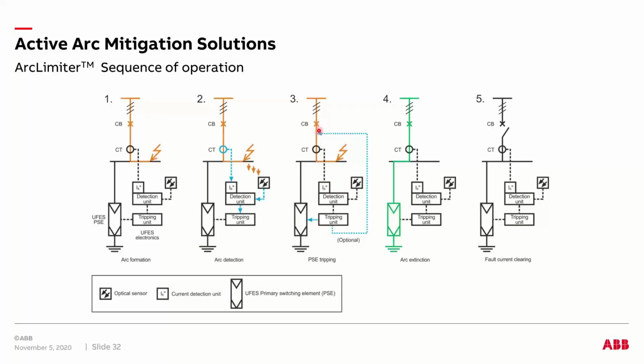So before your 50/51 on the breaker reacts for any kind of fault, in about 4 milliseconds, you are sending a trip signal to your breaker to open. So, depending upon whether it's a low voltage equipment or medium voltage equipment, we can quickly isolate this 3-phase to ground fault by the upstream breaker.